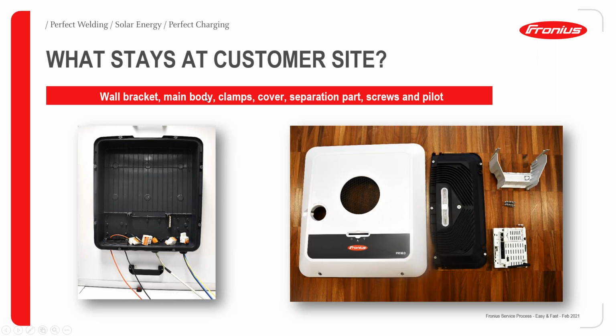So the wall bracket, main body, that's the back, and the clamps like push-in clamps, cover, the DATCOM cover, the separation part of the pilot and the connection area, and then the screws and the pilot. These are all the things which should be retained from the faulty inverter. In case there is something wrong with the wall bracket, the front cover or the DATCOM cover, then you will order them as separate parts. It's not like an inverter exchange.